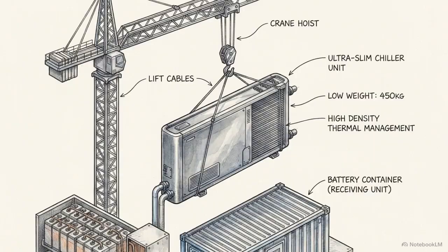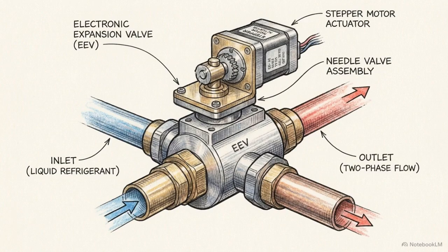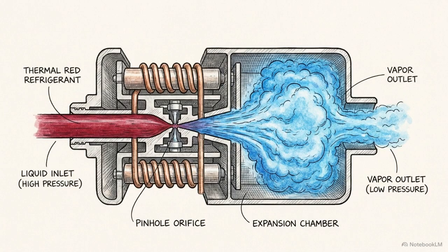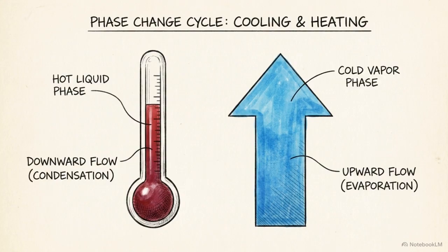Finally, the refrigerant, now a warm liquid, passes through an electronic expansion valve. This valve drops the pressure of the fluid instantly, expanding it back into a freezing vapor, ready to absorb the next cycle of heat. The secondary loop is an engineered mechanism that uses phase changes to forcefully move heat in the opposite direction of the natural temperature gradient.